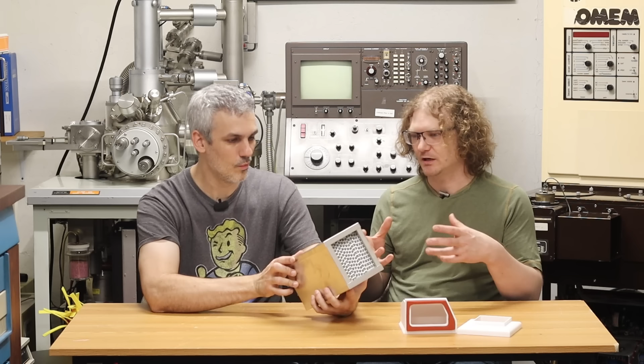We need to glue the two end pieces onto the brand new HEPA filter, and to make sure they stick properly, the first step is to sand down the mating surfaces to get a nice key for the epoxy to grab onto. After a thorough cleaning with canned air and alcohol, we're going to use a 2-part epoxy that should create a very strong airtight seal.